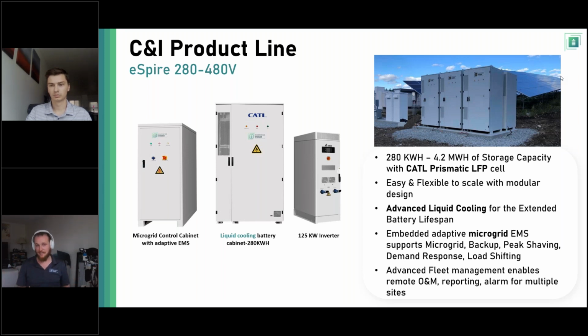That extends the life of your system. The liquid cooling is 3 times more effective at removing heat from the cells than HVAC fans blowing on the system. The standard warranty is 10 years, but with liquid cooling we anticipate the system lasting much longer than the warranty. It depends on how aggressively you use the battery in terms of cycles per day, but it's rated for 6,000 cycles at 90% depth of discharge. At 1 cycle a day, that works out to about 15 years of use.